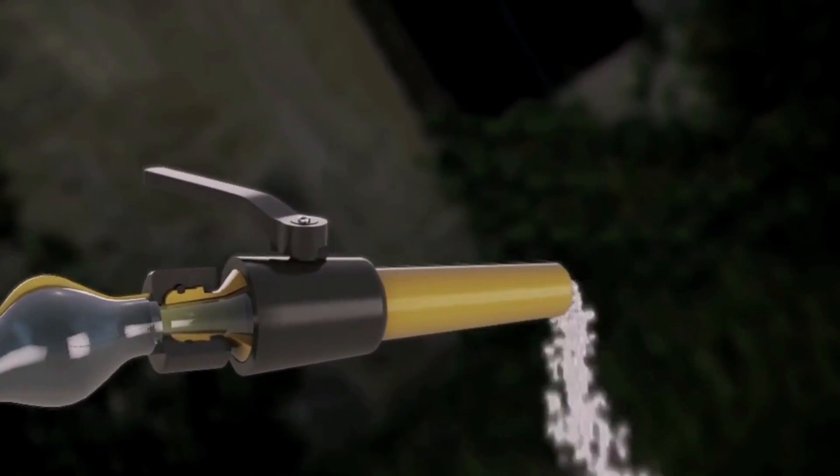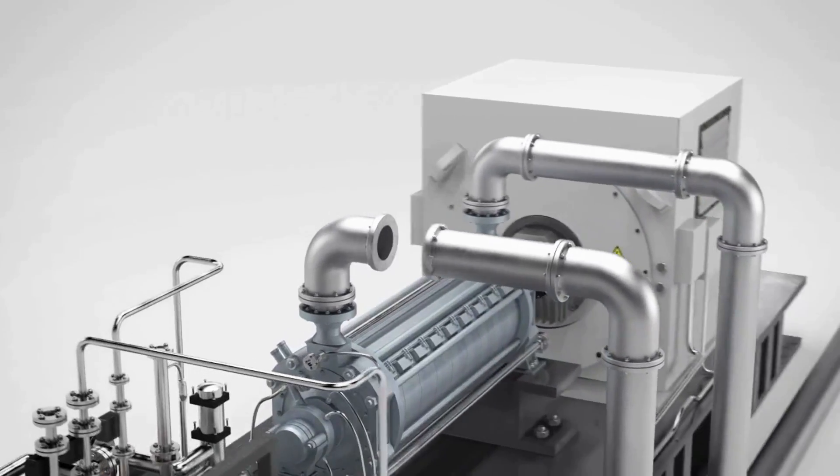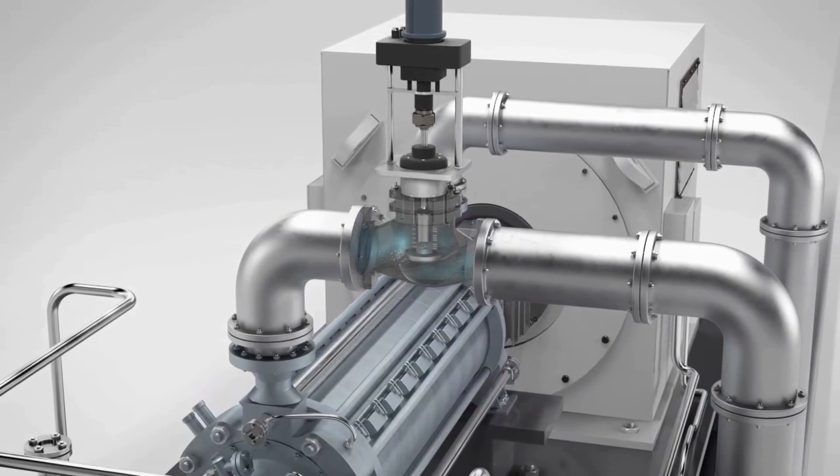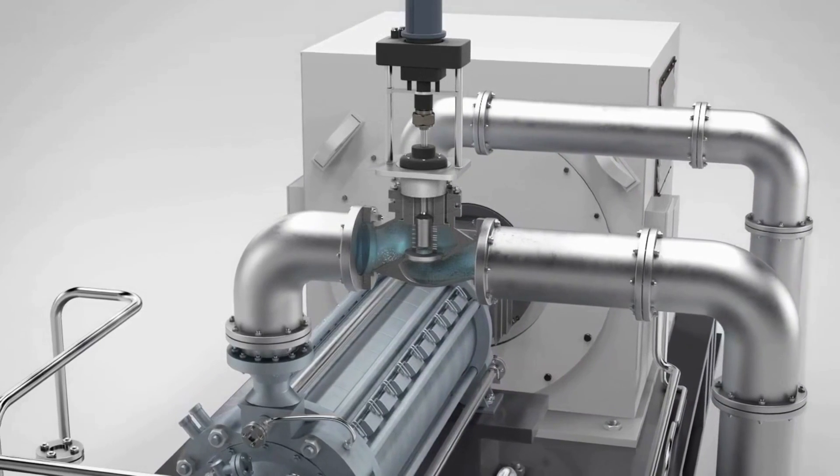While the pump speed remains constant, a throttle valve in the feed water circuit generates resistance in order to reduce the flow volume. The result is increased pressure in the water supply line.